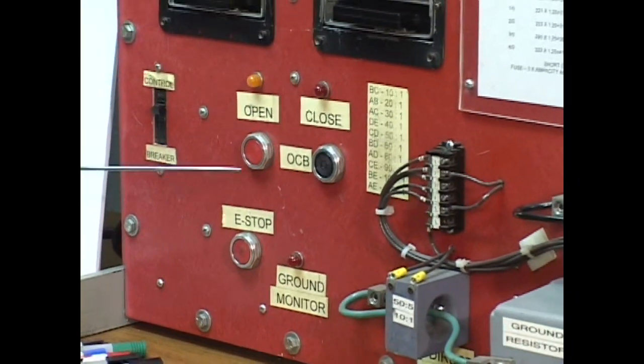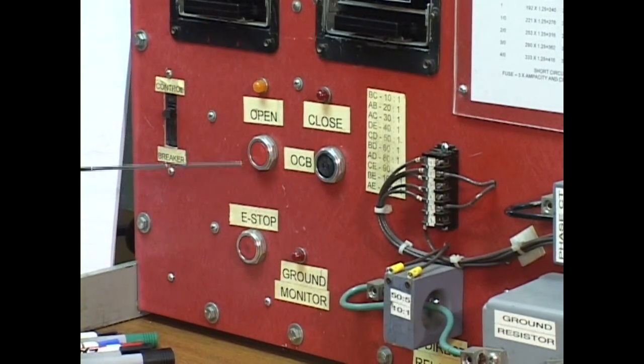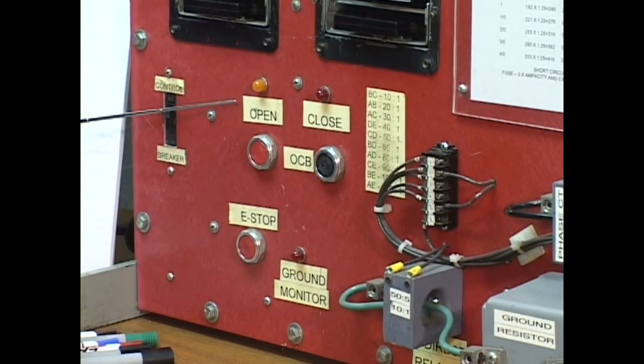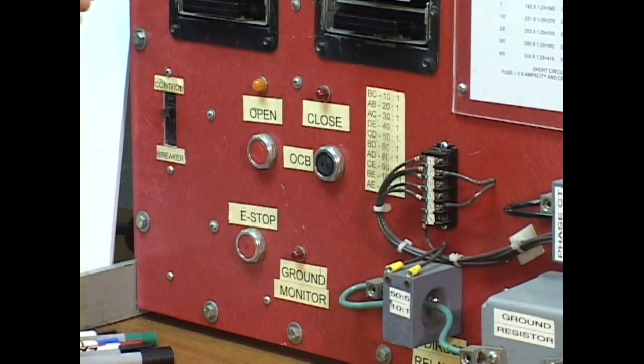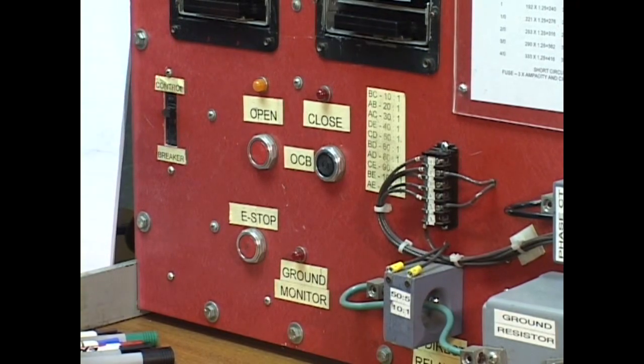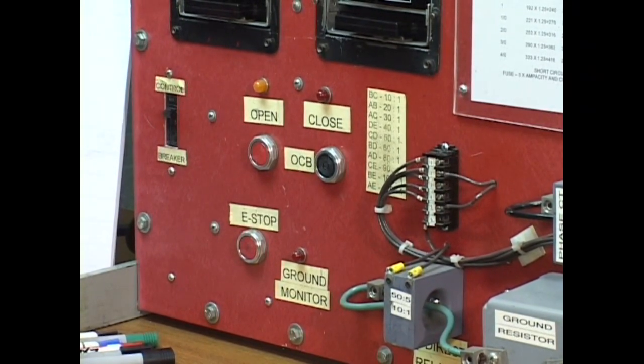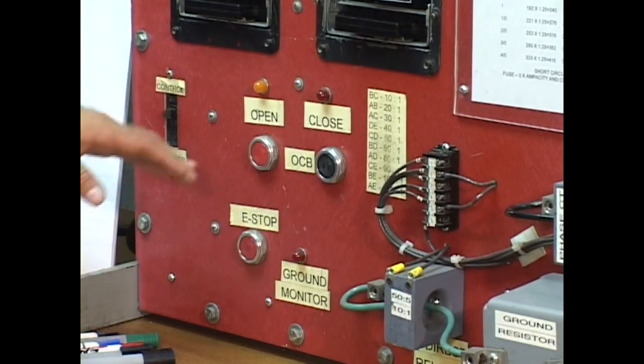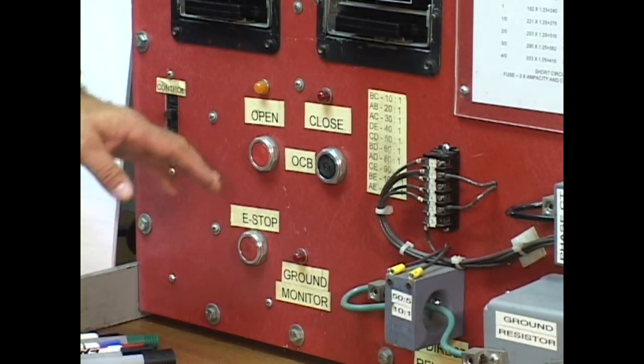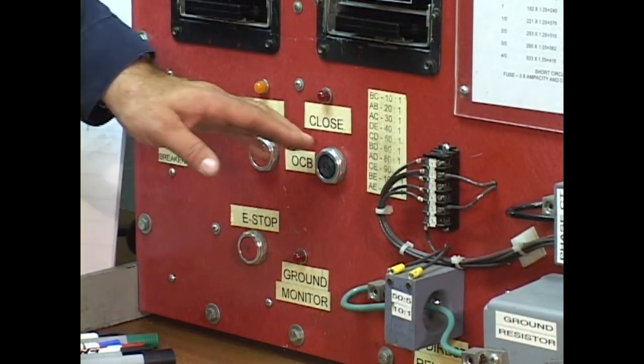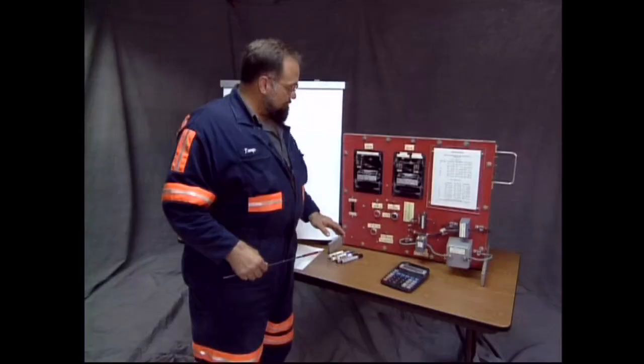Okay, we have OCB switches with lights that show either open or closed. OCB, oil circuit breaker. Open means the power is off, the breaker is open. Closed means power is on, the high voltage circuit is complete, power is going through the breaker. These lights here show open or closed. The red button is to open it, to turn it off. The black button closes it, turns it on.